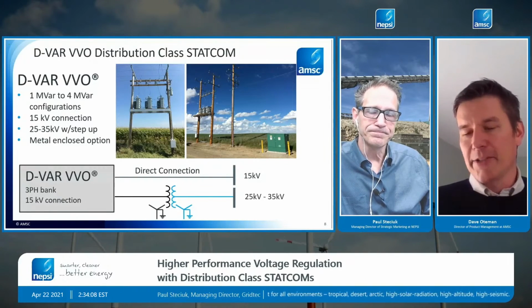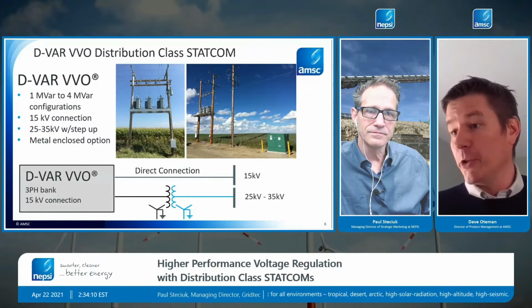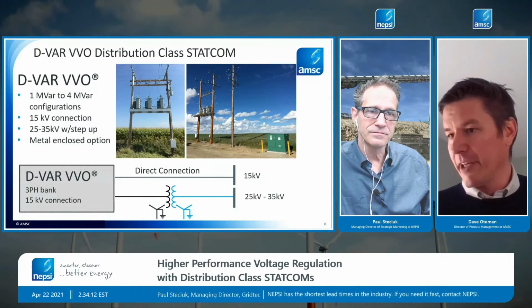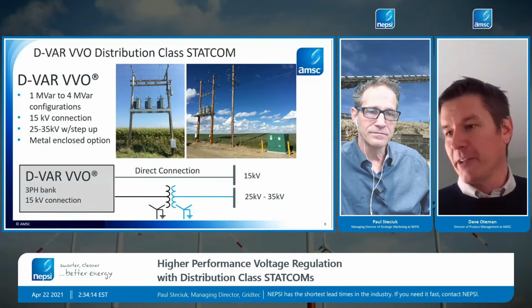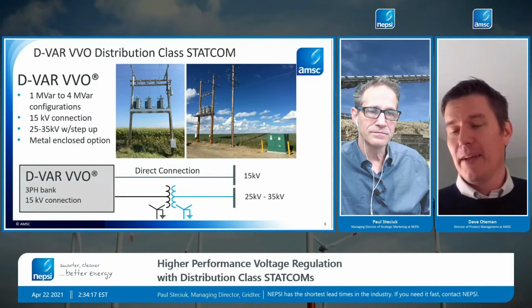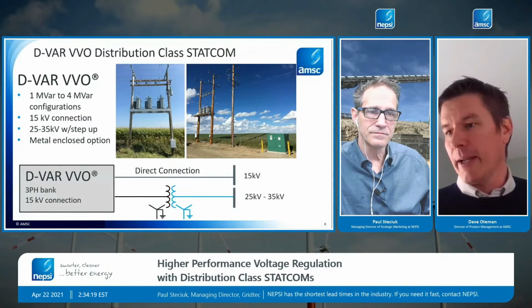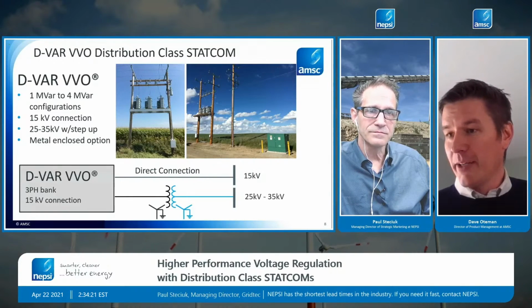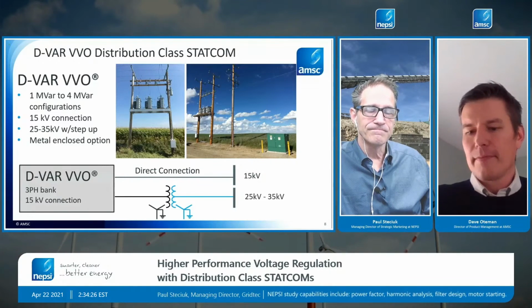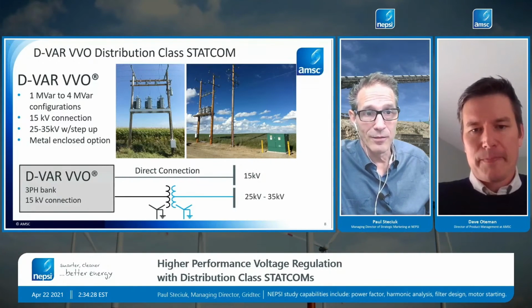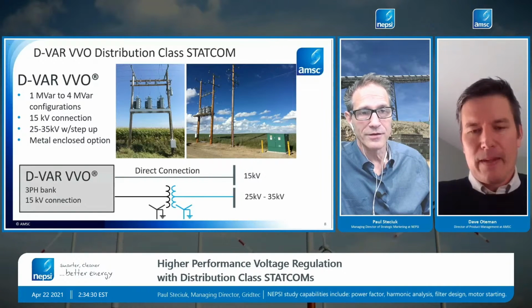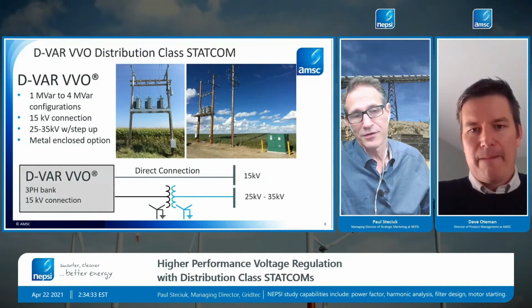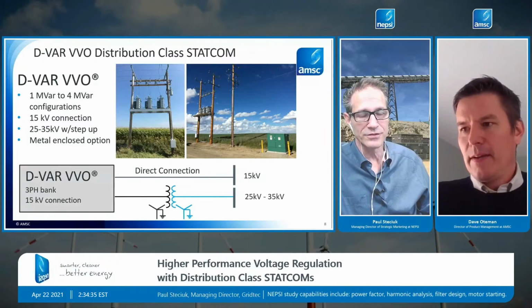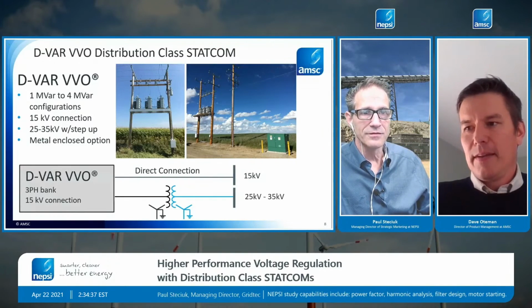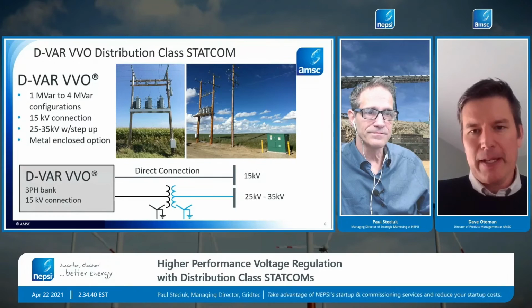I should also mention single phase. We have installations on single phase laterals. If you have a long single phase lateral, for example with a lot of rooftop solar coming in on it, this can be a nice way to manage the voltage on that lateral, and help balance the voltage back at the connection point onto the main feeder, maintaining voltage at that location.